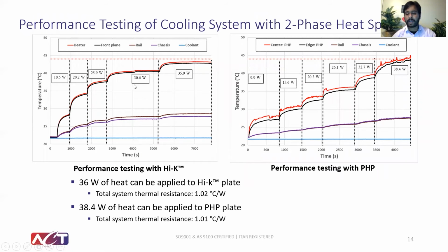In the case of high K plate based cooling system, up to 36 watts of heat can be applied. And the total system thermal resistance was around 1 degree C per watt. So this is basically more than 50% reduction in overall system thermal resistance compared to the baseline. In the PHP based cooling system case, a little over 38 watts of heat can be transported.